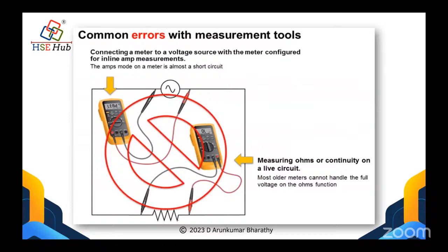So incorrect usage is the first reason. The second, most importantly, is not inspecting before use. Physical inspection is very important for any equipment, but especially for test and measuring equipment, since people may use the same instrument for a decade or more, 10 to 12 years, often handed down from a senior electrical engineer.